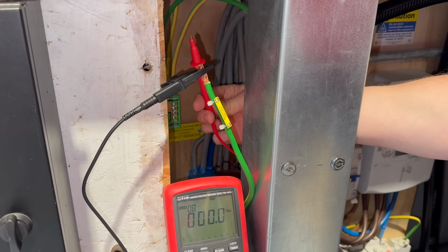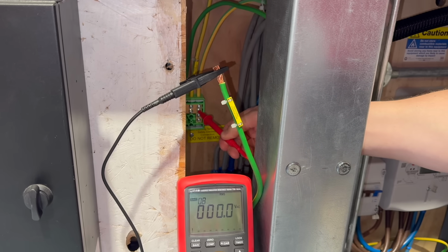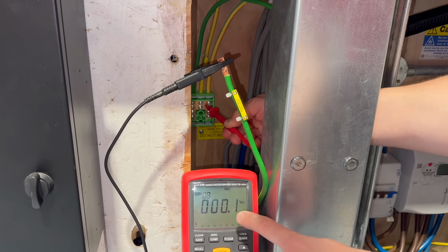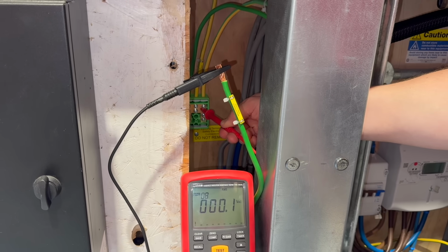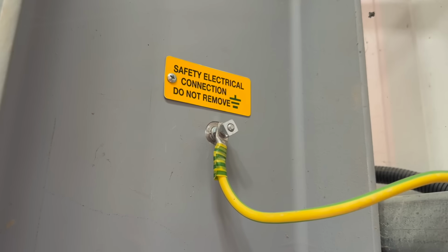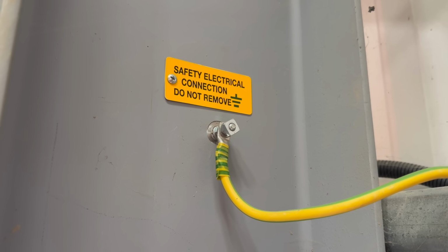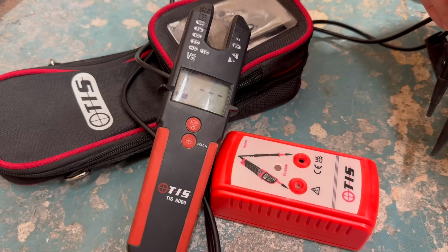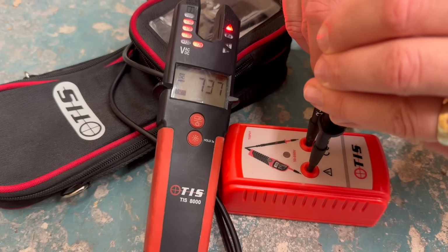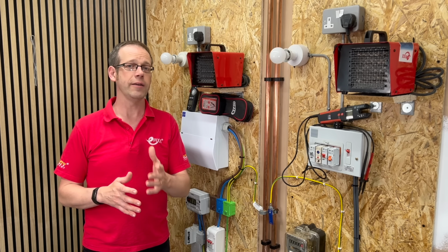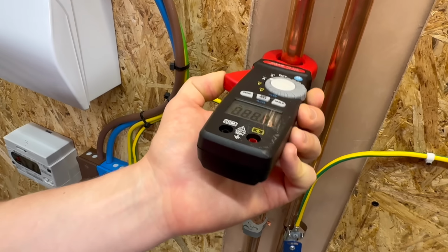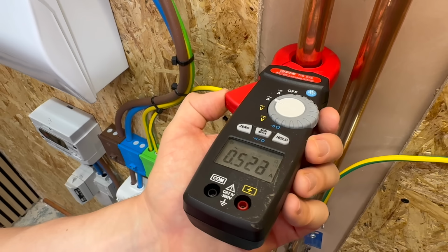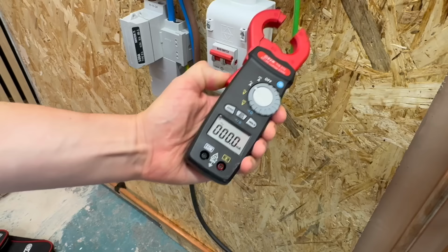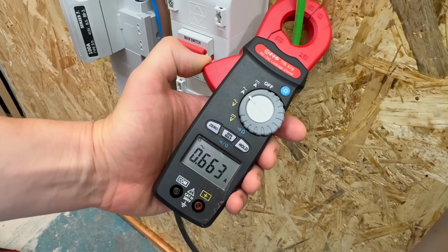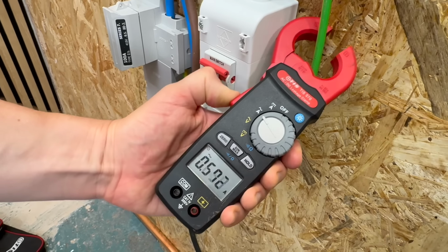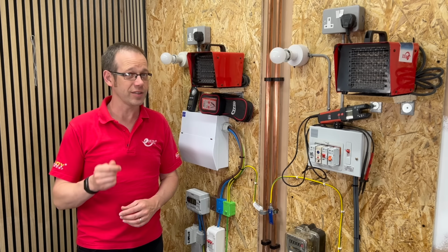But we know it's not a problem, because when we remove the earthing conductor and measure the voltage between it and the earth terminal, the voltage is effectively 0, indicating that there's no serious problem here. And that's where we get our method for making sure that we don't have a live conductor that should definitely be dead. After performing the regular safe isolation procedure on an installation like we've done here, there's a number of further steps that you can take to reinforce your safety. The first is to get your clamp meter around any extraneous conductive parts that you can, like water and gas pipes, and around the bonding and main earthing conductors. If there's current flowing through any of them, then that may be an indication that there's an issue. But as we've seen in our headquarters, it's not a guarantee that there's a problem.